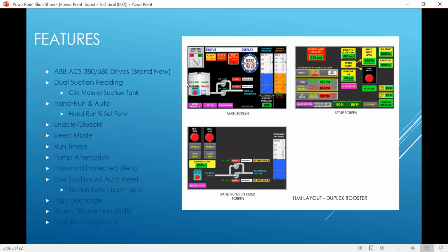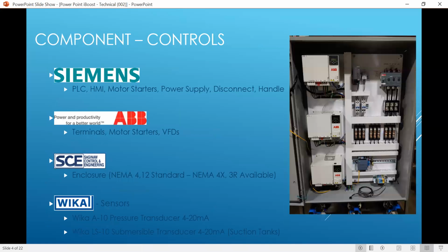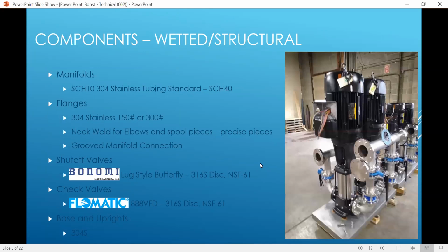Our sensors on there are also WIKA controls. So just that we have also the transducers on everyone. I jumped past a little bit here. Sorry. Components, as far as your wetted and structural, our manifolds are usually Schedule 10 304 stainless tube. And then we can jump up to Schedule 40 if there's a need for that. But typically your Schedule 10, which is rated to 600 PSI, is probably adequate for most systems.